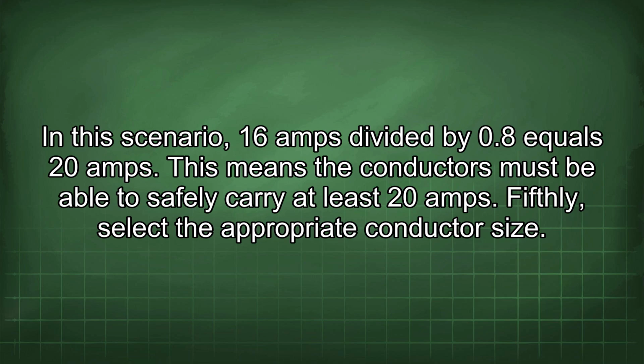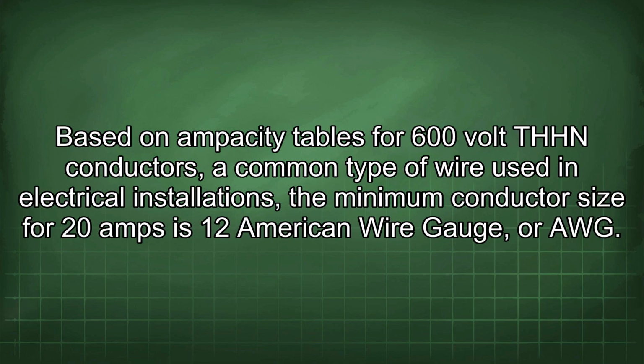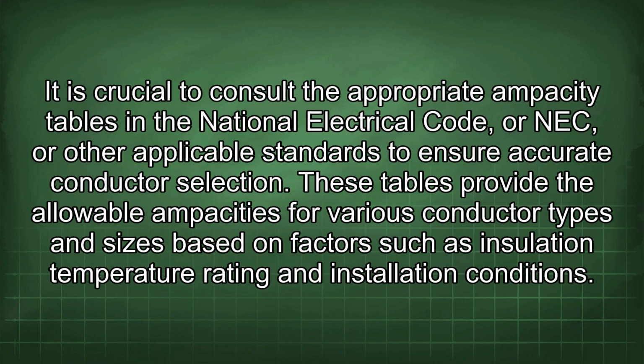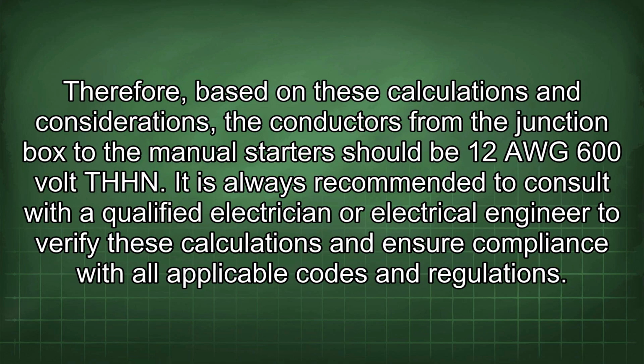Fifthly, select the appropriate conductor size. Based on ampacity tables for 600-volt THHN conductors, a common type of wire used in electrical installations, the minimum conductor size for 20 amps is 12 American Wire Gauge, or AWG. It is crucial to consult the appropriate ampacity tables in the National Electrical Code, or NEC, or other applicable standards to ensure accurate conductor selection. These tables provide the allowable ampacities for various conductor types and sizes based on factors such as insulation temperature rating and installation conditions. Therefore, based on these calculations and considerations, the conductors from the junction box to the manual starters should be 12 AWG 600-volt THHN.